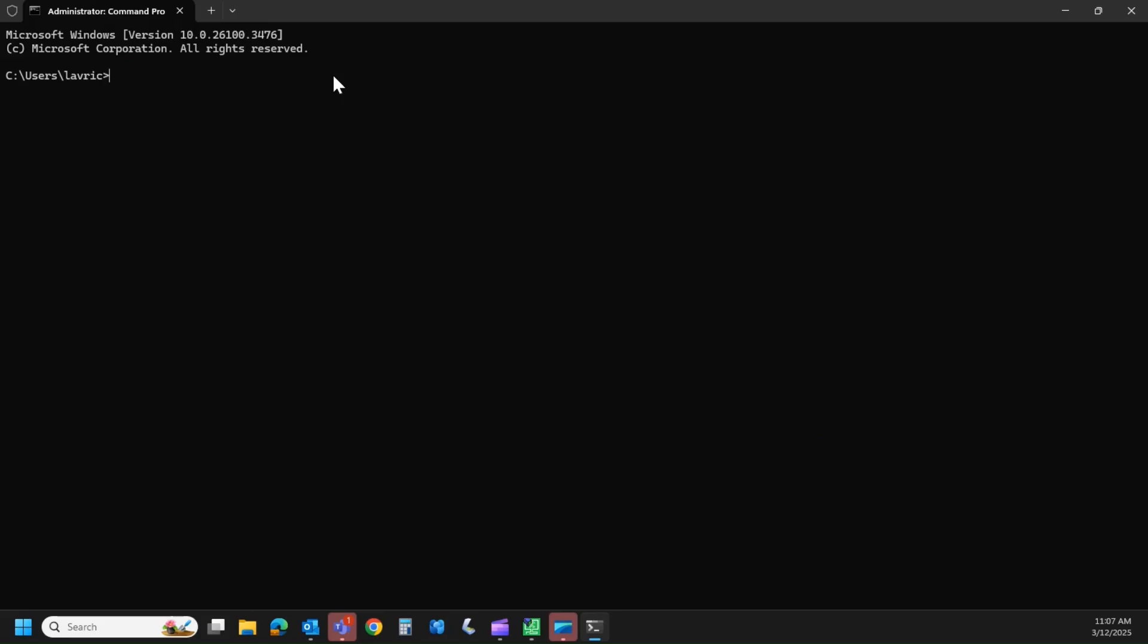So out of the box, the IP address for the Mini 8 is going to be 192.168.111.222. That is the default. So on your PC end, you would have to have these first three fields the same, 192.168.111, and then something other than 222. So I've already got mine set up.